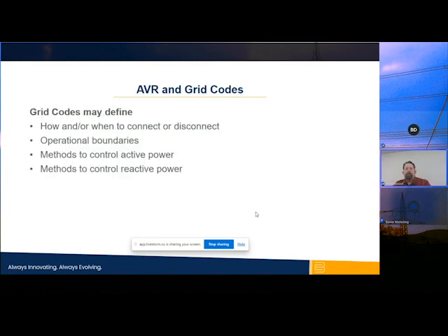How does the AVR really interact with the particular grid codes? And what are the things we need to look at, and what can the voltage regulator itself control from the grid codes? They are how and when to disconnect or reconnect to the grid. So we're going to talk a little bit about that. We're going to talk about the operational boundaries of that synchronous machine. The voltage regulator is obviously controlling the voltage, but more directly, we're controlling the reactive power component of that synchronous machine at that intertie point. So we're going to look at those operational boundaries of that synchronous machine and how the AVR interacts with that.